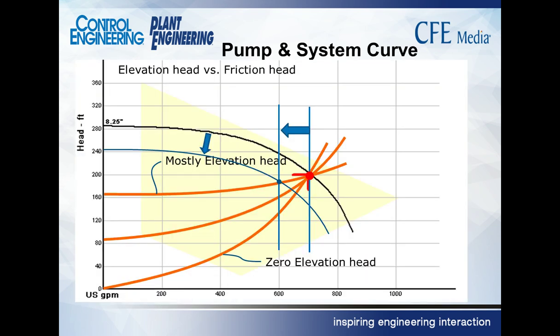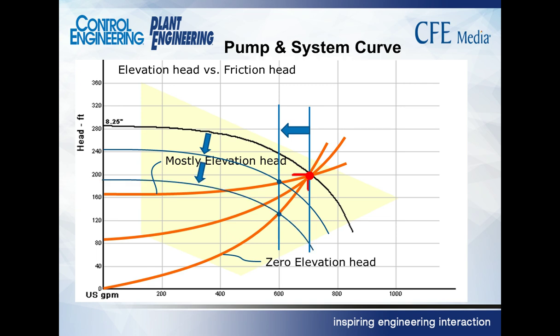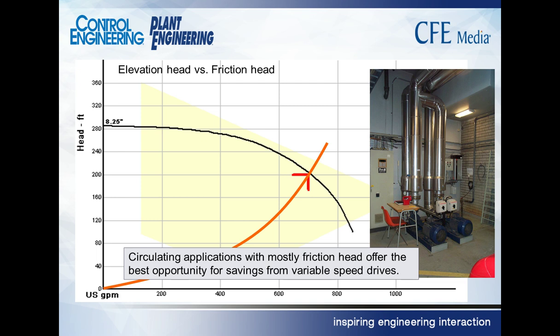That affects how much energy can be saved by reducing speed. In the case with mostly elevation head, it doesn't take a lot of change in speed to reduce that flow rate quite a bit. So there's a change in head to do that, but it's not very much. Okay, it's a pretty shallow curve. On the other hand, the zero elevation head, to make that same change from 700 gallons per minute down to 600 gallons per minute is a much greater change in the amount of head. In both cases, the amount of flow changes from 700 to 600. With the shallow curve, not much change in head. With a much deeper, steeper curve, much more change in head.